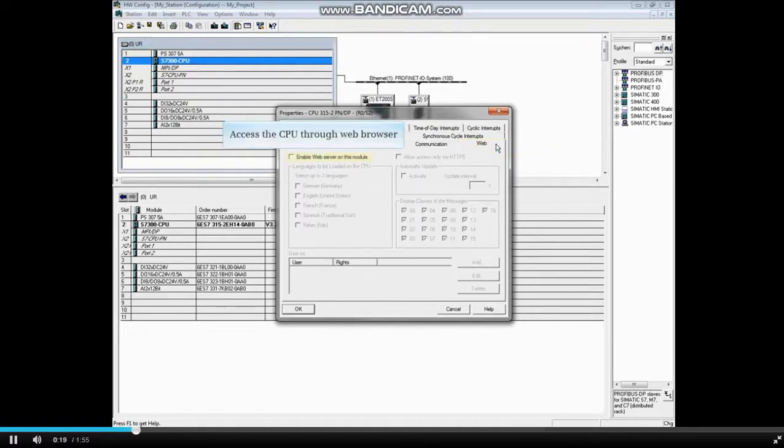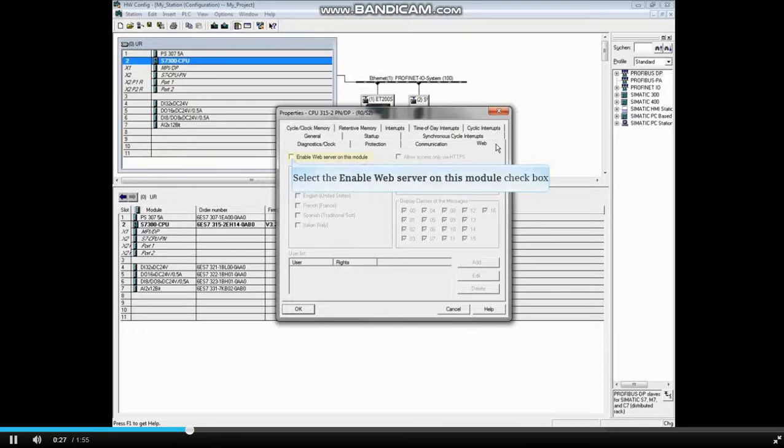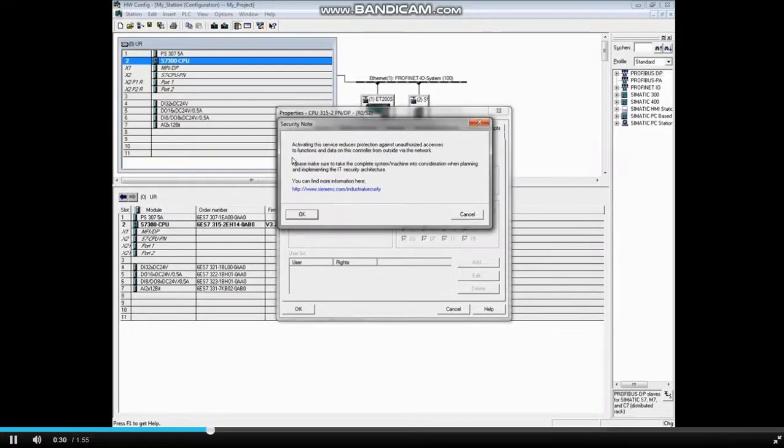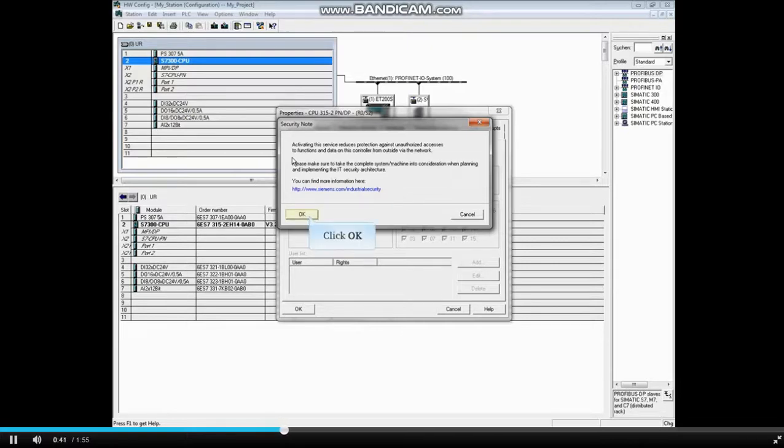Select Enable Web Server in order to access the CPU from a web browser. When the hardware configuration is saved and compiled and downloaded, this will download web pages to the CPU. You will see a message advising that you may make the CPU vulnerable to outside access and that you should take necessary security precautions. There's also a link for help on security. Click OK if you want to continue.